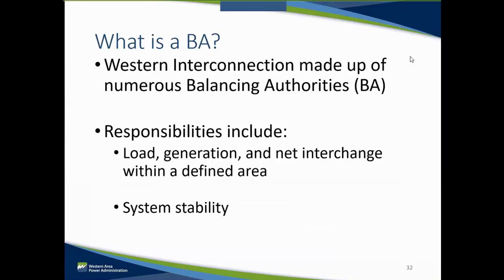Today in the Western Interconnection, the interconnection is maintained by a number of individual entities called balancing authorities. Balancing authorities account for all load, generation, and net interchange. There are a specific set of resources and interchange meters assigned to each BA. The BA is responsible for ensuring system stability by constantly balancing the generation, load, and interchange within its designated area.